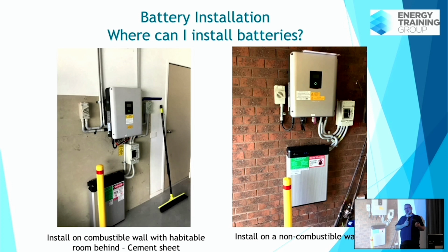We've found with battery installation we're probably 95% of the time putting them inside a garage. On the odd occasion we've put them outside, the customer has to build a little house to cover up the battery and keep direct sunlight off it. However, that little house has to be open all around the outside because you want airflow - you don't want to build a sealed shed around it because again the battery's going to get too hot.